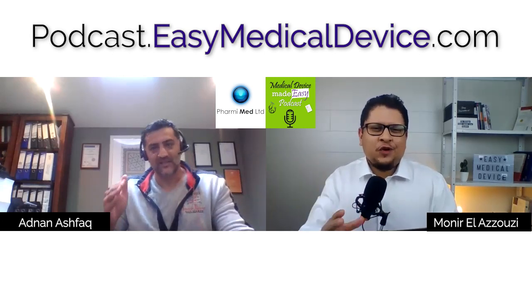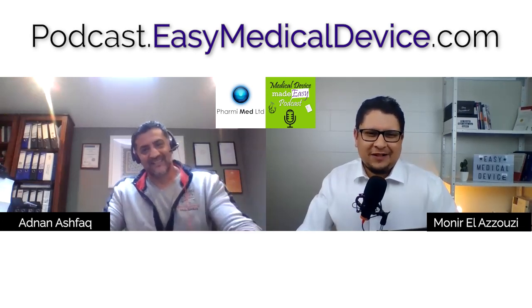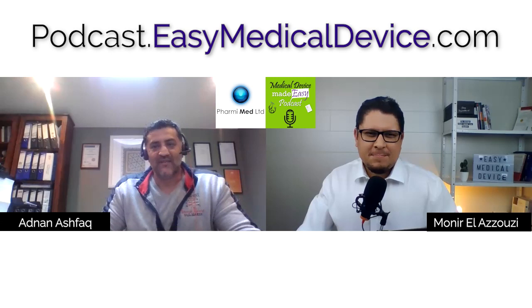So let's go to OQ, as you mentioned before. The OQ for me is the heart of validation, not only because it's in the middle of IQ, OQ, PQ, but because the purpose of operational qualification is to stress test the equipment, to take it to its outer limits. So let's say you have pressure, temperature, and time as parameters — you want to ensure you have an operating window that allows you to manufacture within it, tested within the extremes: an upper limit and a lower limit.